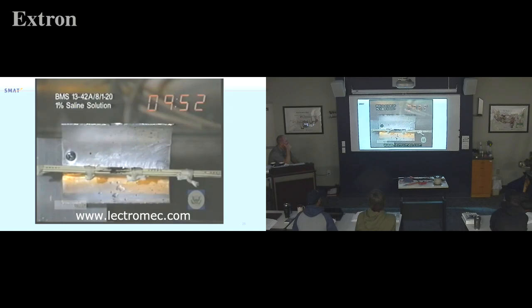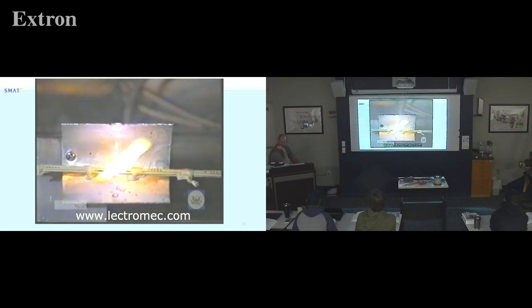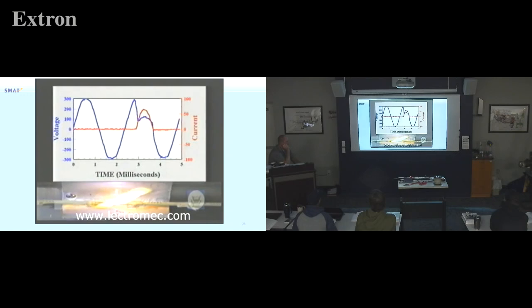Soon, a larger flash of light with an accompanying popping sound occurs. As time progresses, the pops and flashing become more frequent. Examination of the oscilloscope recording of voltage and current from a flash event reveals a classic arcing waveform. The blue line represents the voltage between the two damaged wires as time progresses. The first cycle on the left shows a normal 400 Hz sine wave.